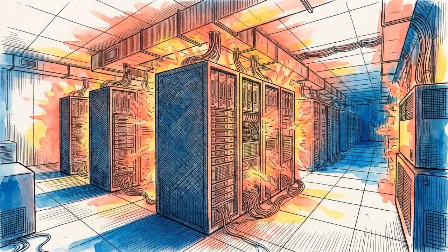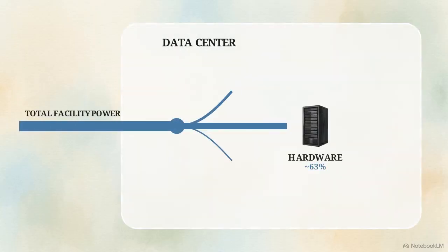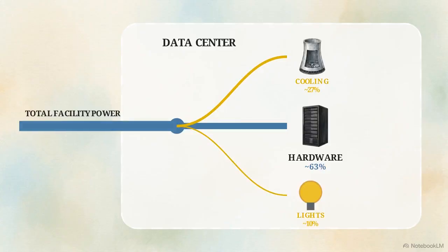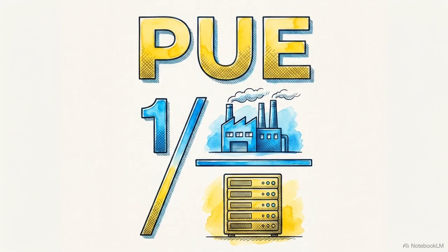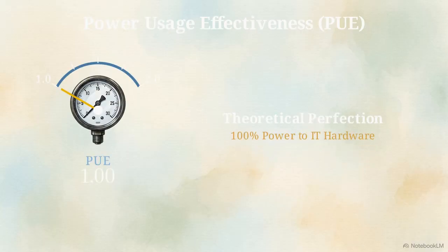To manage this heat, the industry first needs a rigorous way to measure how effectively a facility routes power directly to its hardware, rather than wasting it on external operations. The standard metric is PUE, or Power Usage Effectiveness. It measures total facility power compared to actual IT equipment consumption. A baseline score of 1.0 represents theoretical perfection, a state where zero electricity is lost to lighting or external cooling.